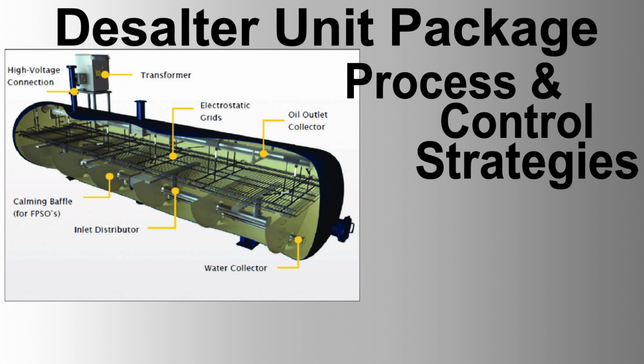3. Cascade control for desalter inlet. Primary controller monitors the crude oil quality and salt content. Secondary controller adjusts the water injection rate and electrostatic field based on signals from the primary controller. Detailed control loop design. Slug catcher to three-phase separator.